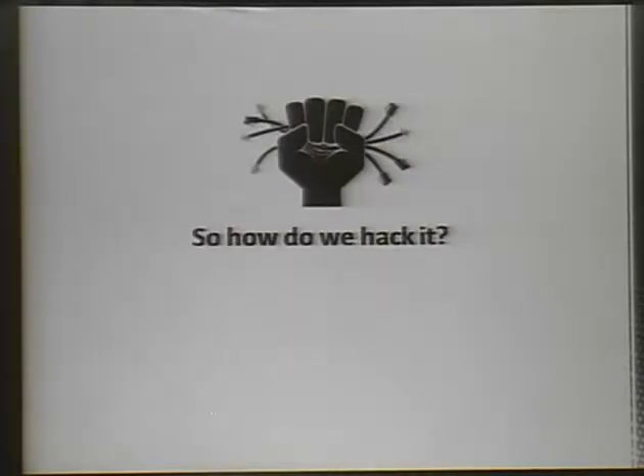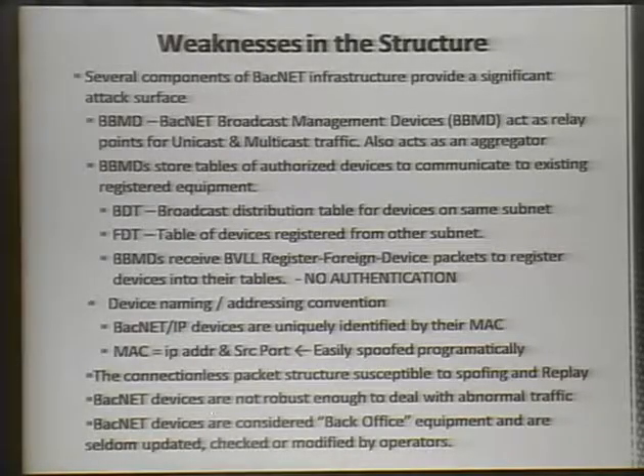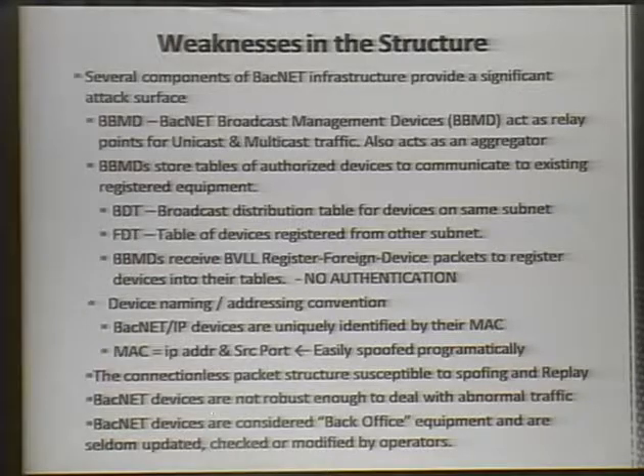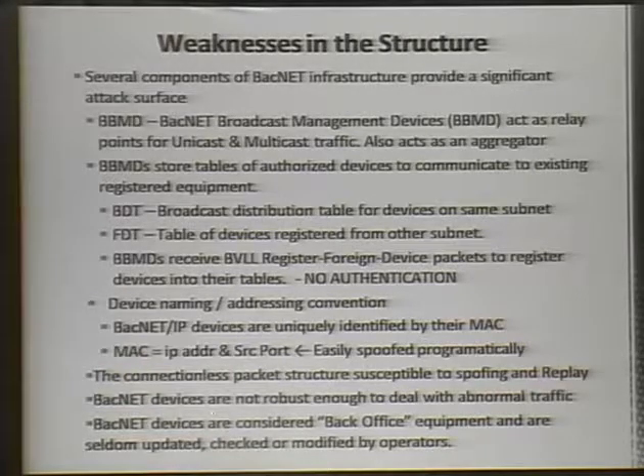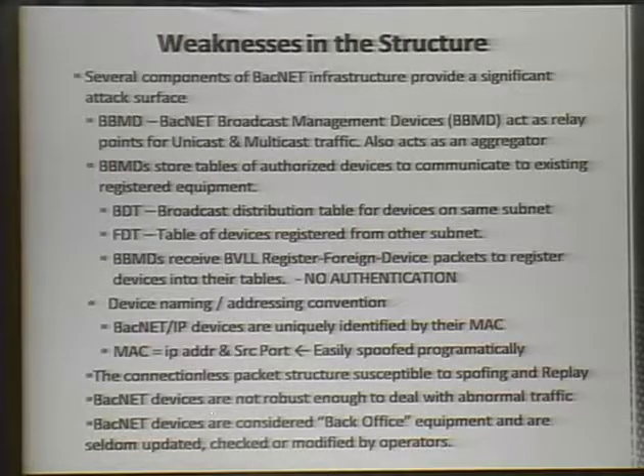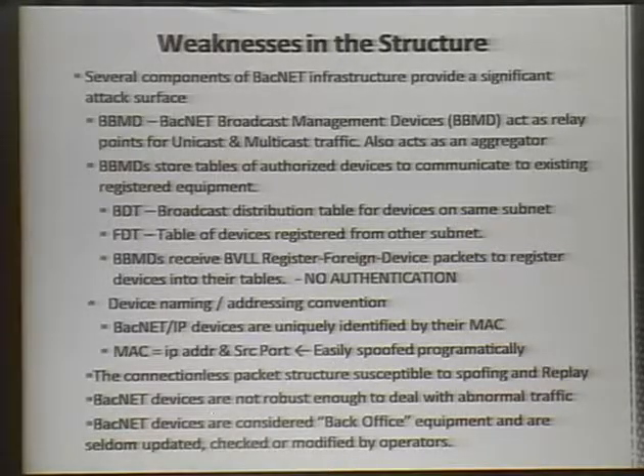So the attack surface: weaknesses in the structure of BBMD devices, the BDT and FDT tables. Most communication here has no authentication — that's where things get tricky. BACnet devices don't have a real MAC address; they use their IP address and a common source port, 47808, for all communication. These are very easy to manipulate from a packet perspective, making it much easier to control things.